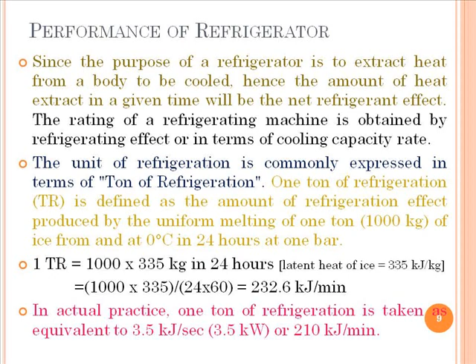So when we go for calculation, 1 TR is 1000 into 335 in 24 hours. 335 is the latent heat of ice. So 1000 into 335 divided by 24 hours into 60, means now we are converting hours into minutes. So our answer is 232.6 kilojoule per minute. If we want to convert that unit into kilojoule per second, again we have to divide it by 60. So the answer is 3.877 kilojoule per second, or 3.877 kilowatt. So in actual practice, 1 ton of refrigeration is taken as equivalent to 3.5 kilowatt or 210 kilojoule per minute.